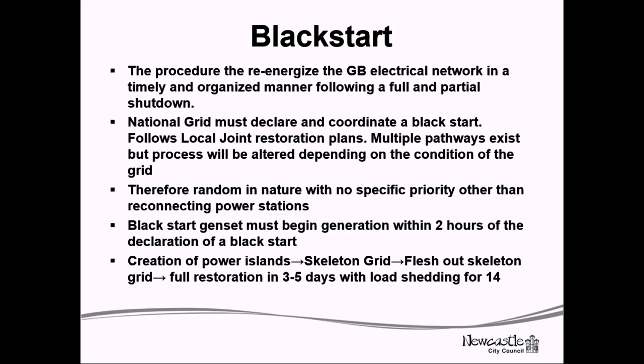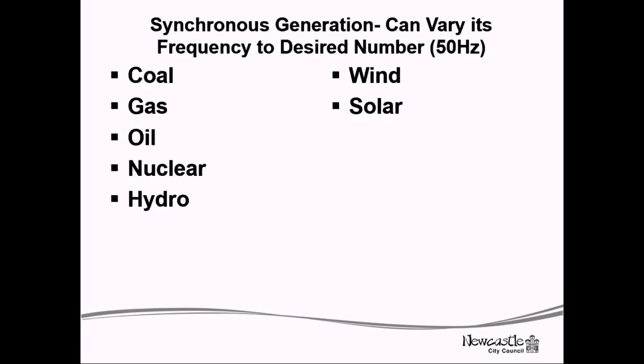A black start enabled generator will normally be coal, gas, oil, nuclear, or hydro. Wind power is good, but it cannot play an opening role in the restoration of power to the country. Normally it's coal, increasingly gas and oil as well. Nuclear is a synchronous form of generation, but once you trip a nuclear station offline, it takes between 48 and 72 hours to get it back on the grid. Then there's hydro, but we're limited because the topography of the UK doesn't allow that much hydro power.